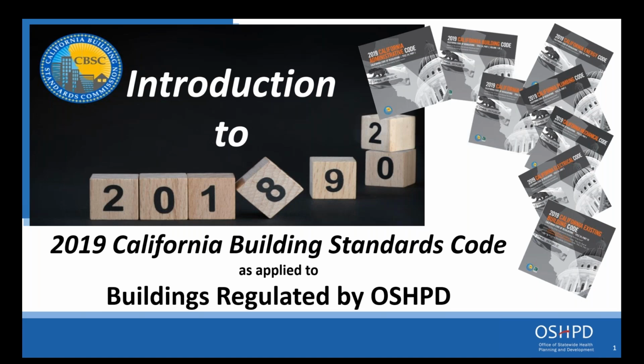All right, thanks, Bill. I have another question for you. This question deals with emergency generators, and the question reads: requirements for emergency generators, 96 hours of fuel storage instead of 72 hours? Do you need a reserve tank for 72 hours beyond what is part of the generator set as required by licensing? Yeah, that's a good question, and Richard touched on that briefly about 96 hours.